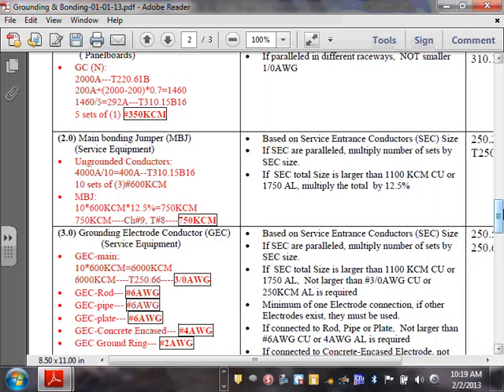So my main bonding jumper and supply side bonding jumper are the same size, and both of them in this switchgear are 750. Have I said that these are the minimum? You could go ahead and do 800 if you want to, right? Do you guys parallel them? Parallel the main bonding jumper? By the way, the main bonding jumper in a switchgear is not a wire. So if somebody says, oh, 750 is really hard to work with, that's because you're inside the switchgear. And the main bonding jumper inside the switchgear has never been a wire. It's always a copper bus bar sized by the manufacturer based on UL. So we don't really have to mess with that.